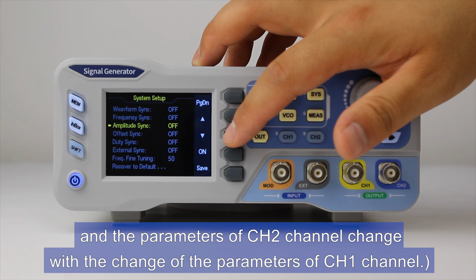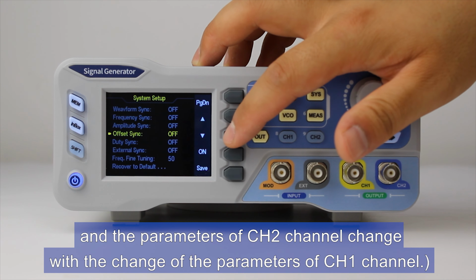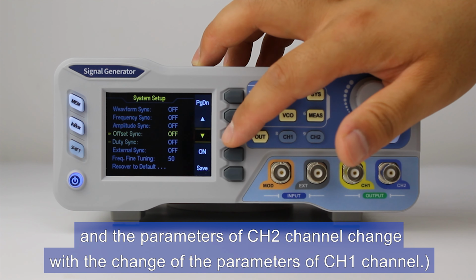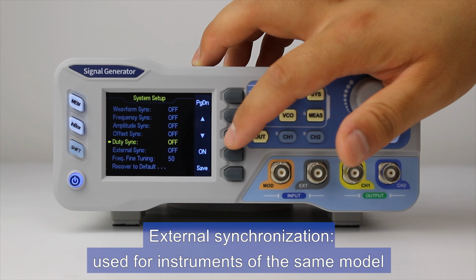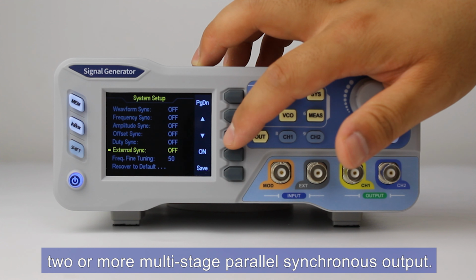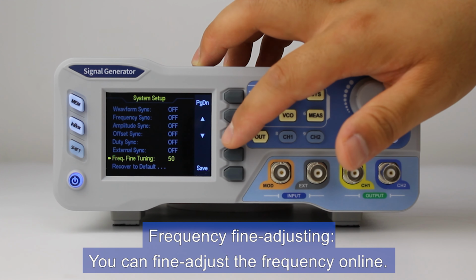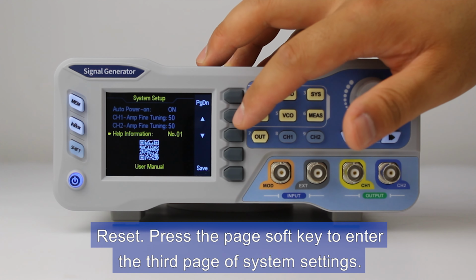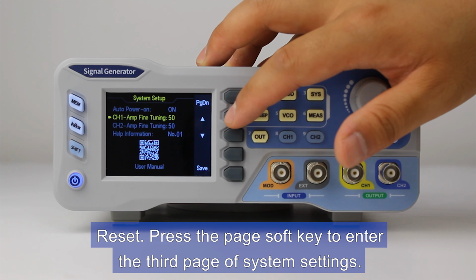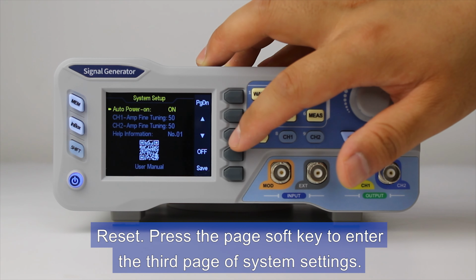And the parameters of CH2 channel change with the change of the parameters of CH1 channel. External synchronization used for instruments of the same model, 2 or more multi-stage parallel synchronous output. Frequency fine adjusting, you can fine adjust the frequency online. Reset, press the page soft key to enter the third page of system settings.